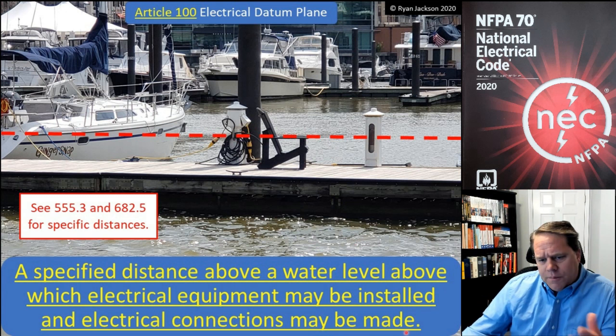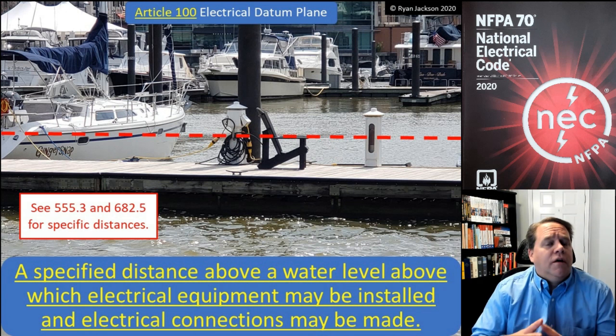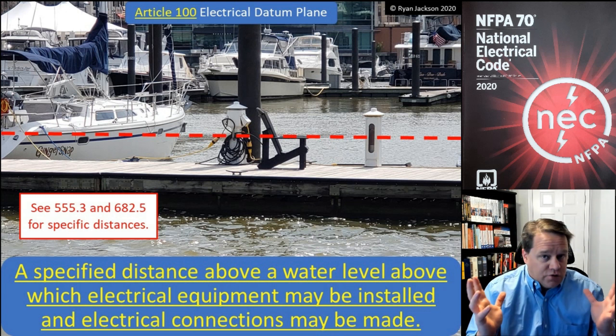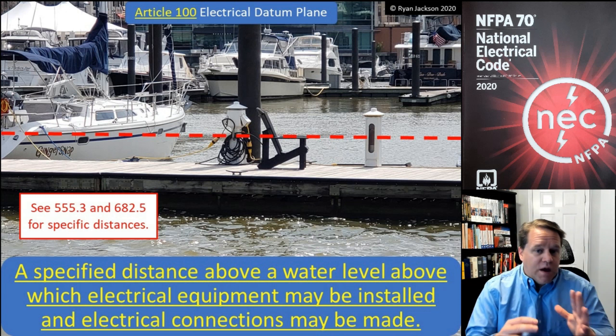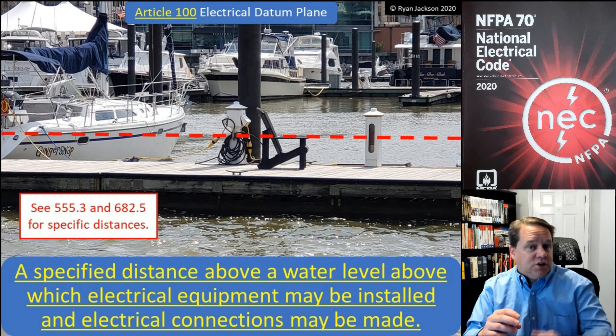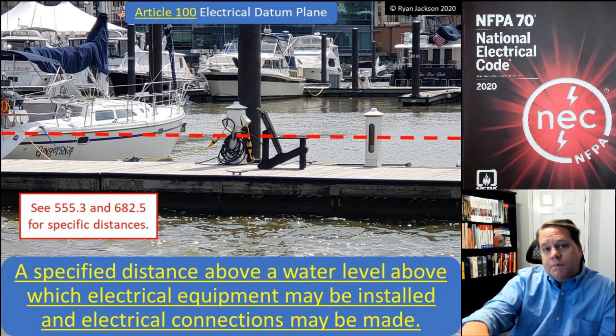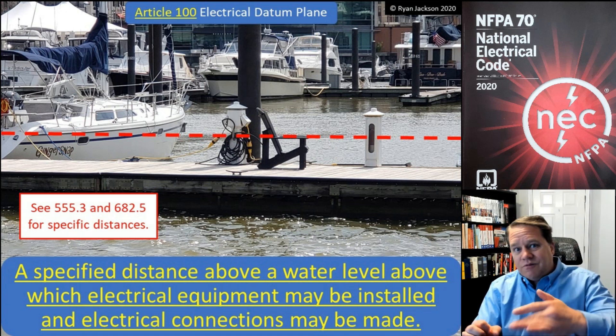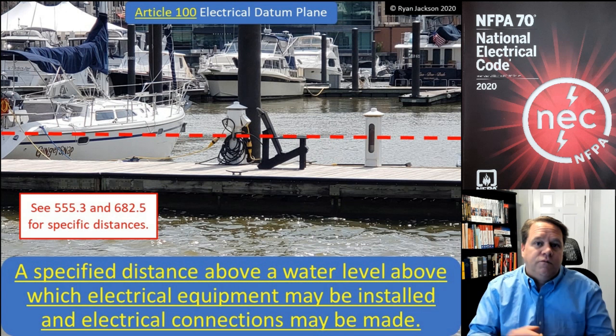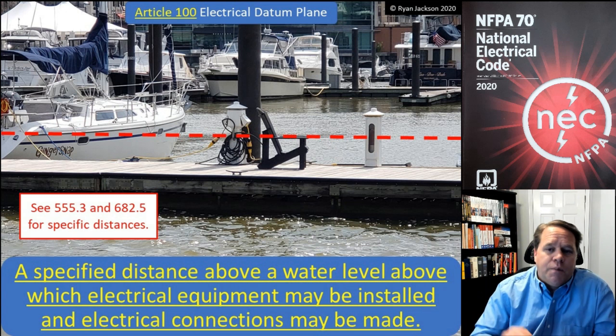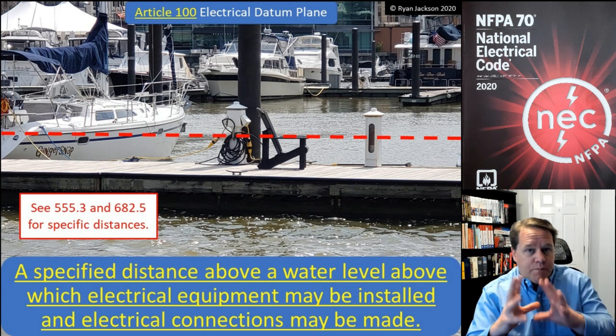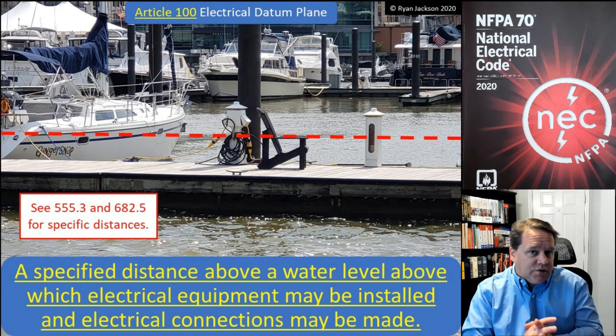The electrical datum plane depends on a few different factors. First, is this area subject to tides? If we have rising and falling tides, that's going to change the electrical datum plane. If my body of water stays relatively the same — obviously lakes and rivers rise and fall — but whether or not you are subject to tidal fluctuation has a big factor on your electrical datum plane.